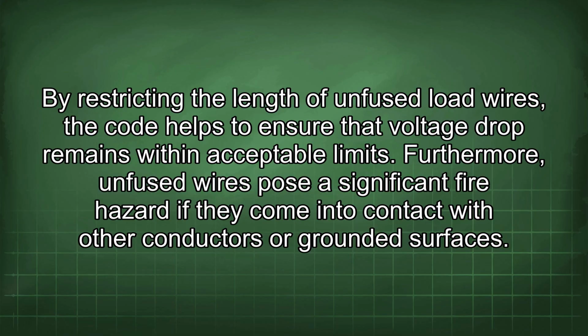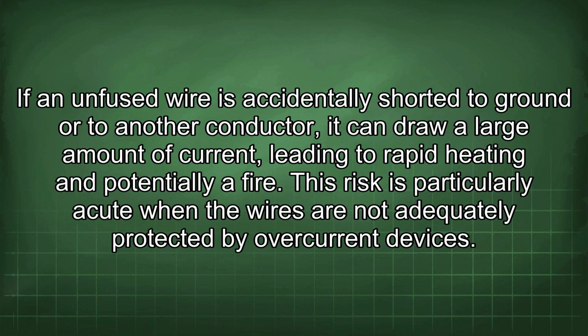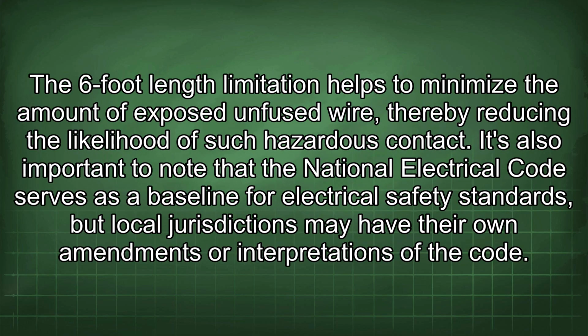Furthermore, unfused wires pose a significant fire hazard if they come into contact with other conductors or grounded surfaces. If an unfused wire is accidentally shorted to ground or to another conductor, it can draw a large amount of current, leading to rapid heating and potentially a fire. This risk is particularly acute when the wires are not adequately protected by overcurrent devices. The 6-foot length limitation helps to minimize the amount of exposed unfused wire, thereby reducing the likelihood of such hazardous contact.